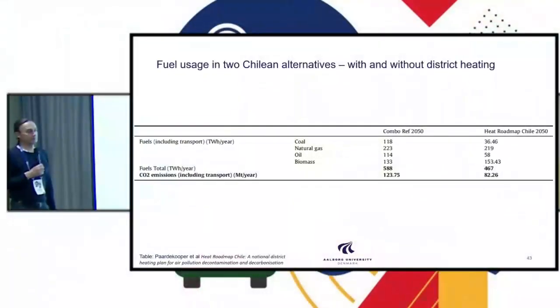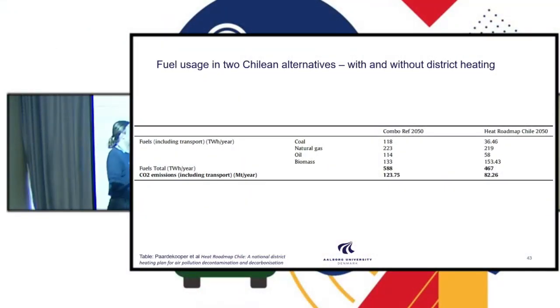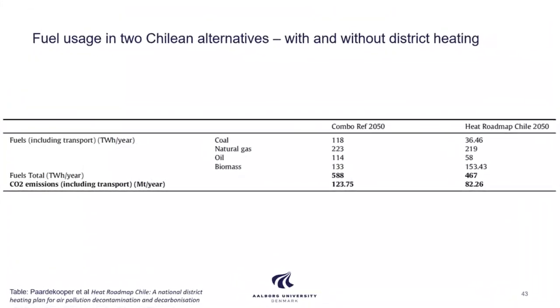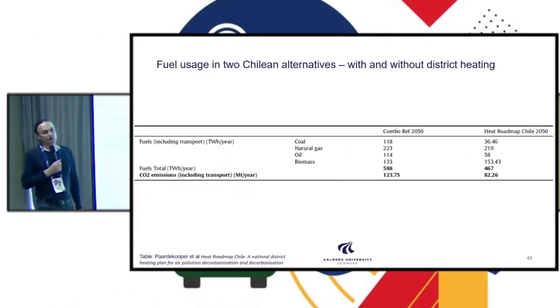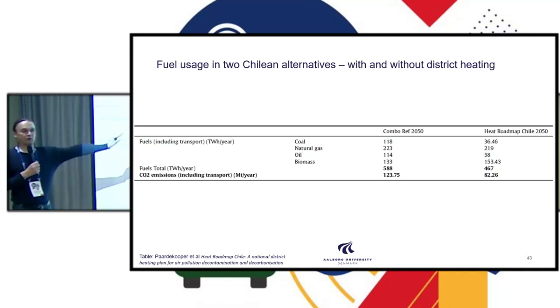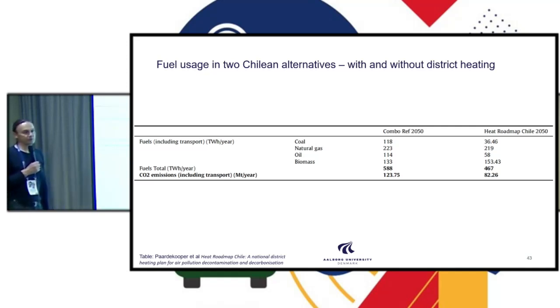Second question: the biomass shown on the last slide is still part of the system but in a different shape. Paul's answer: in the reference scenario biomass is used to a very large extent in individual boilers, whereas in the Heat Roadmap Chile scenario it is used in CHP stations — a biomass boiler with a steam turbine — and as district heating boilers with gas purification. So the same fuel is used in different, cleaner units.